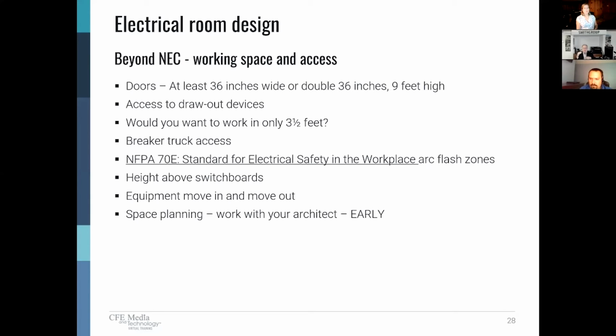We talked about the height above switchboards, that dedicated space, right? You can go 6 feet or to the structural ceiling. My recommendation is that you should try and get at least 2, if not 3 feet minimum above any major piece of switchgear, any major switchboard. That allows you to get conduits bent in and out. Yes, I've done pull boxes on top of gear to get past that, but really work with your architects to define the height of that room and get good dedicated clearance above there, and work with them early in the planning. A lot of times these room spaces are designed before the electrical engineer gets involved. The engineer has to be involved during the planning phases.